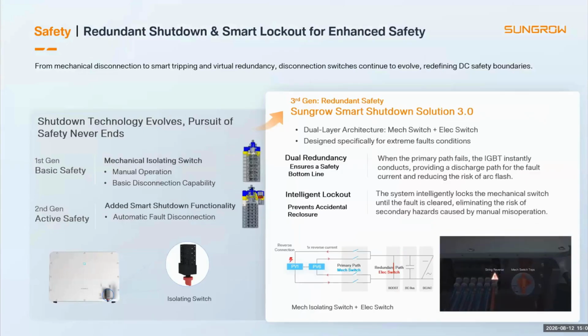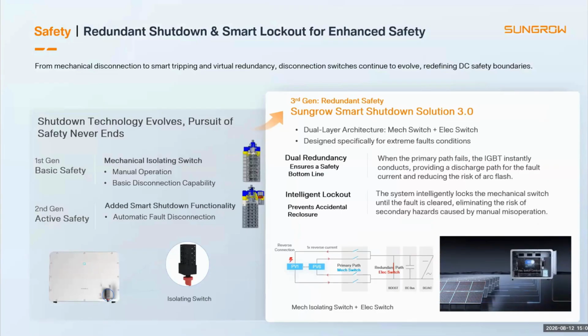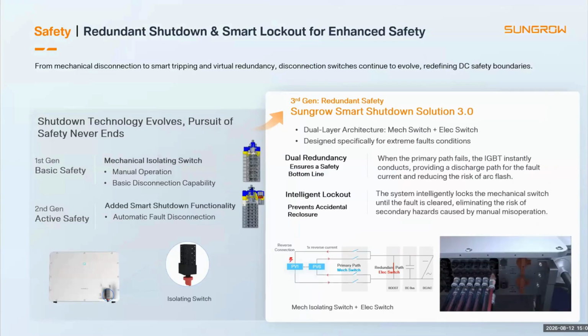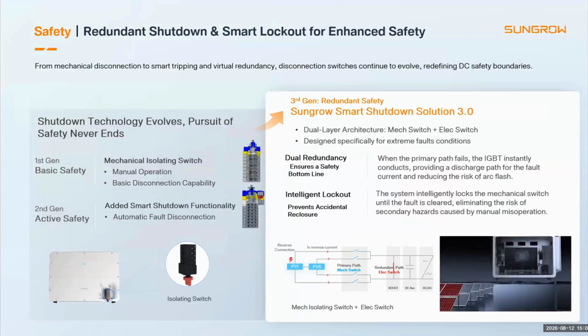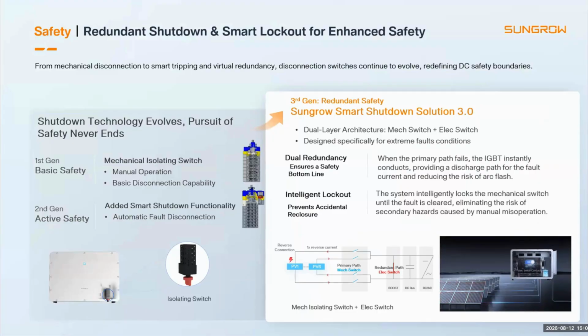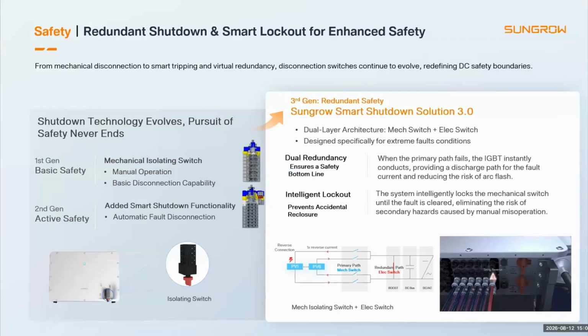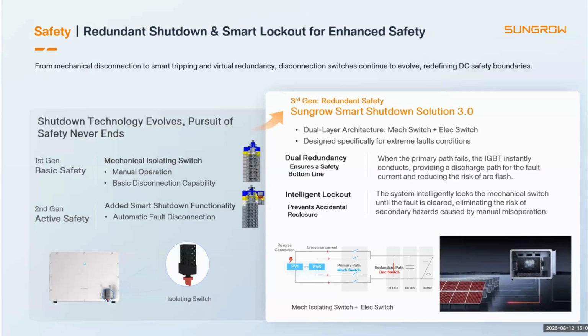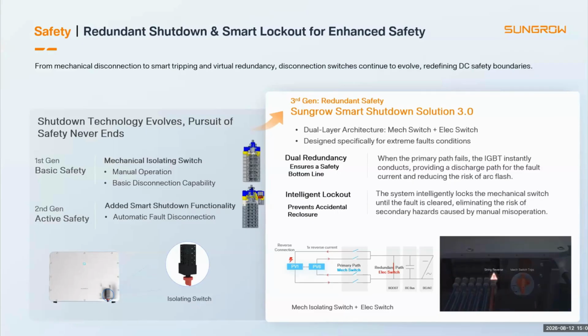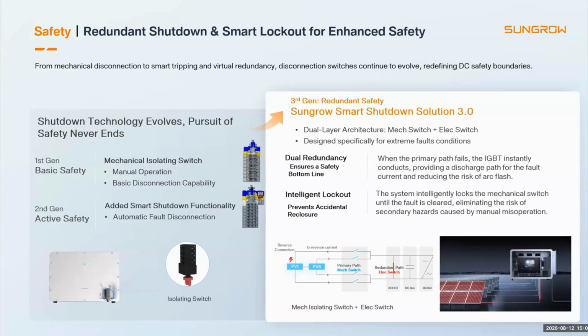Now we move to safety. Sungrow's smart shutdown solution, the third generation, combines a mechanical switch and an electronic switch. If the primary path cannot interrupt an extreme fault correctly, the electronic path can provide additional protection and help reduce arc flash risk. The system also includes intelligent lockout, preventing accidental reclosing before the fault is cleared. So the focus is not only fault disconnection, but the safe and reliable isolation.